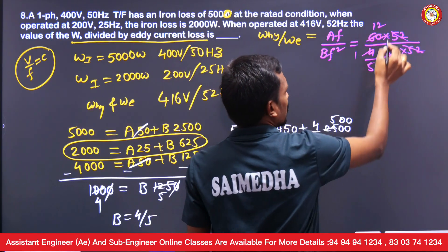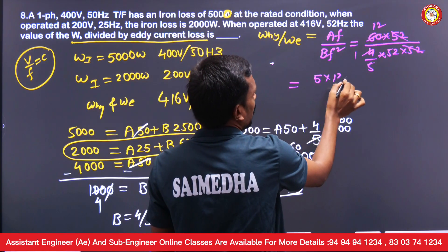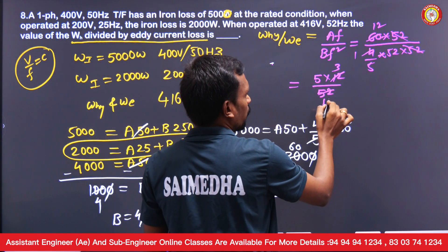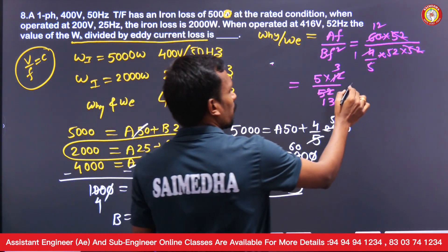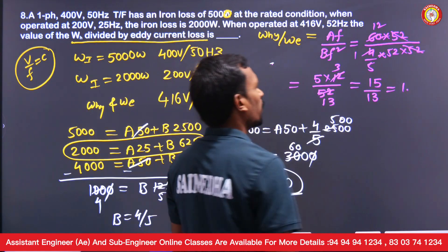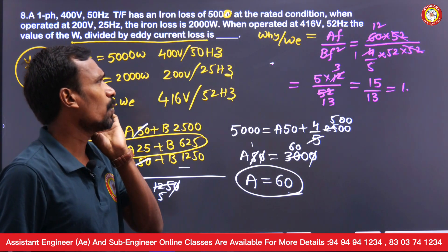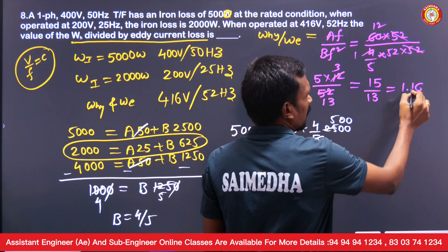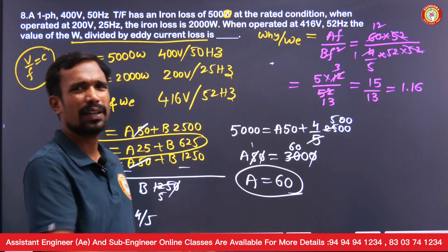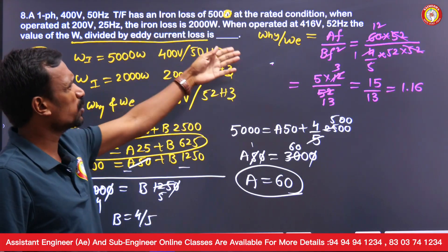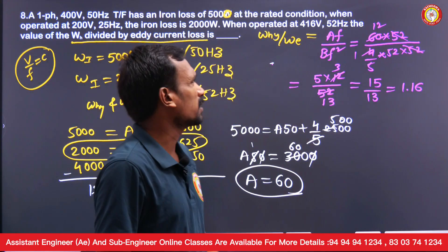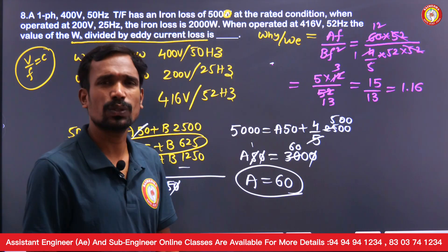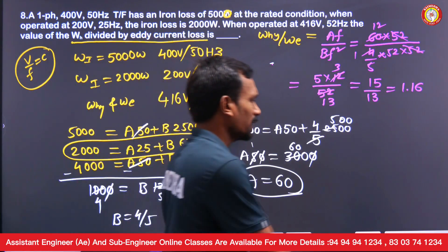After cancellation, the ratio simplifies to (5×12)/52 = 60/52 = 15/13 ≈ 1.15. You don't need to separately calculate hysteresis and eddy current losses — just use a·f divided by b·f² at 52 Hz and simplify directly.